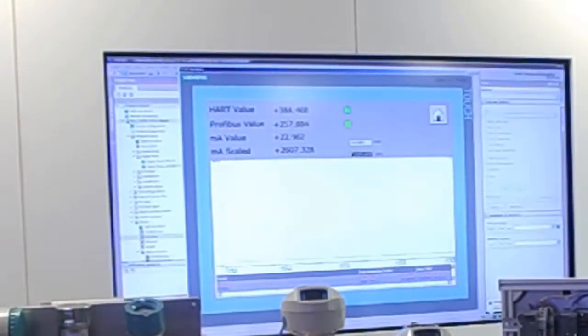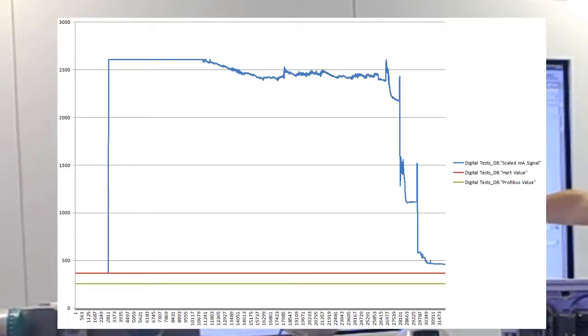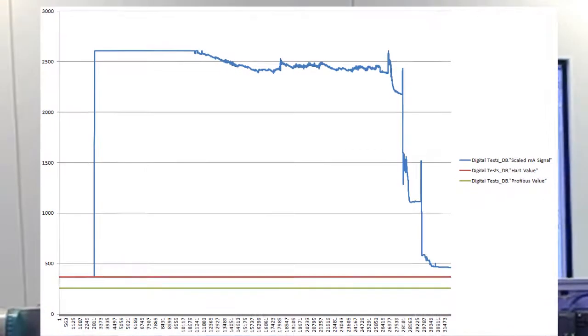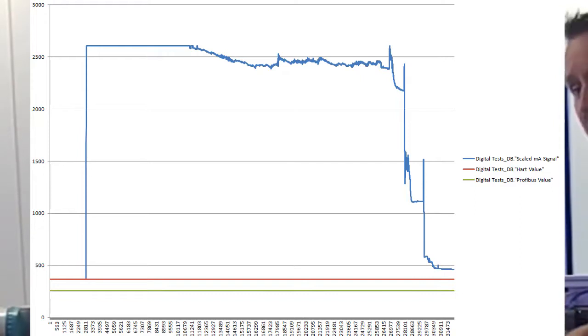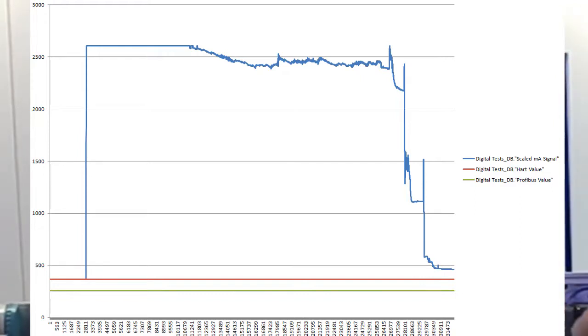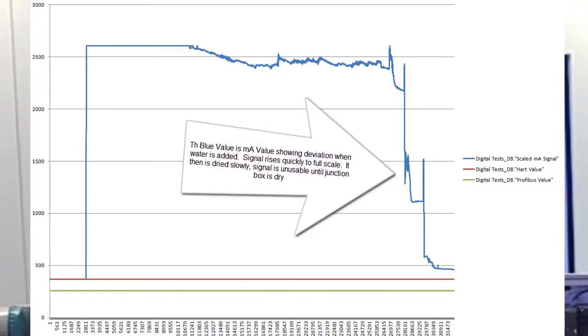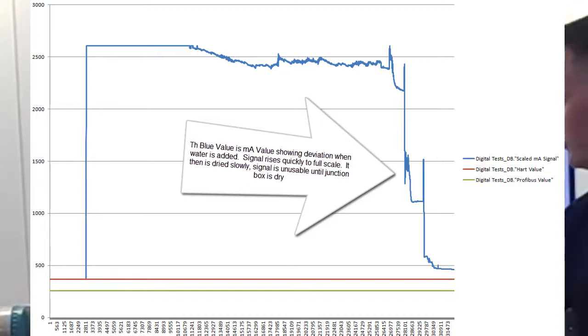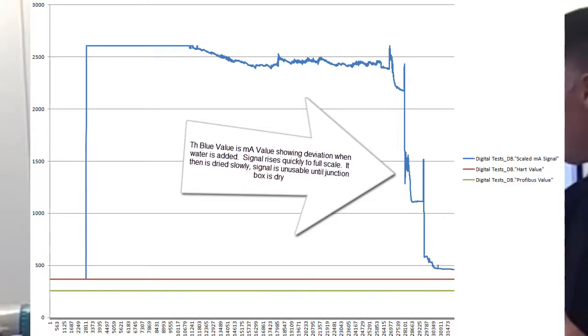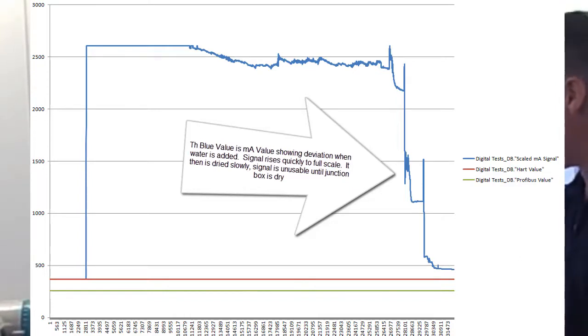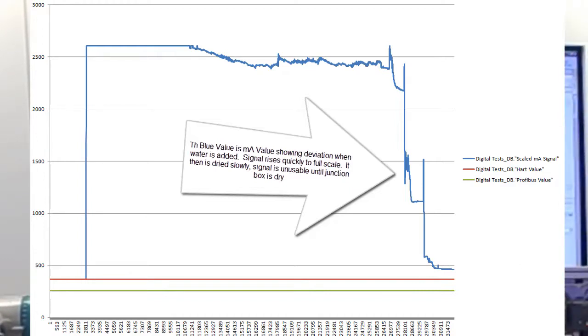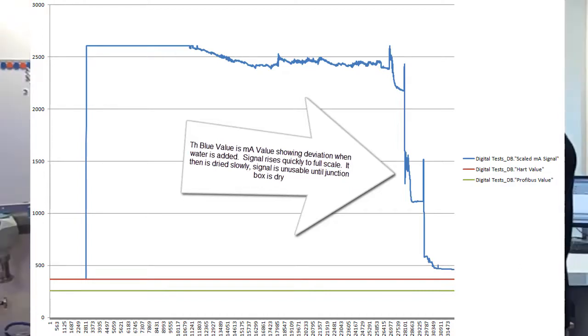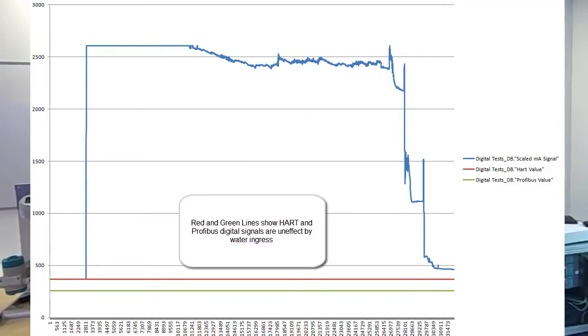And what you'll see straight away in the background is my milliamp value has gone full scale as it's shorted. It is extreme. If we were doing condensation it would be a slightly different value, but I've lost my process value. It's not going to a fail safe condition because as far as the 250 is concerned it is happy. It's encapsulated. It's sending out the right signal. This is purely to do with the cabling of the 4-20. So remotely we have no indication. And if I was a little bit less extreme on the watering so I sprayed this, I would see the value starting to jump around rather than being saturated.